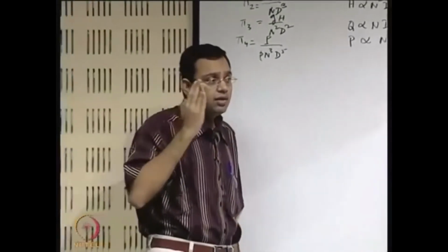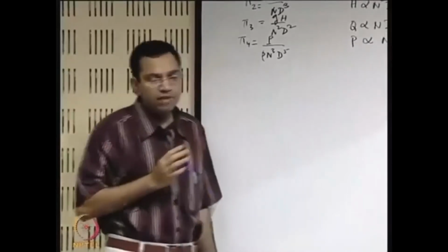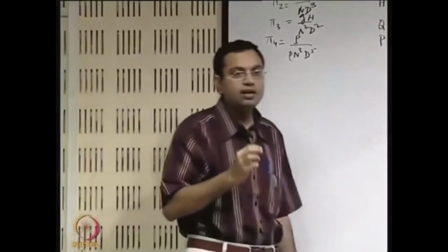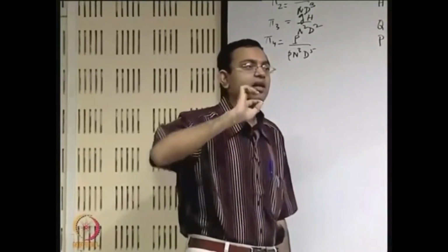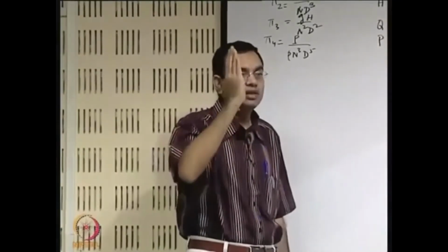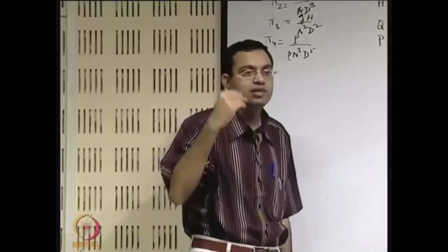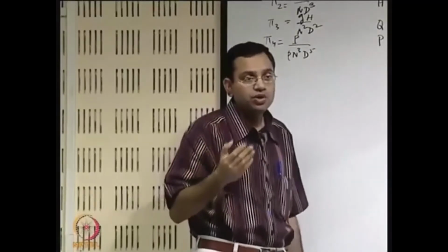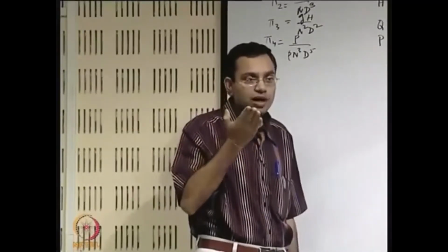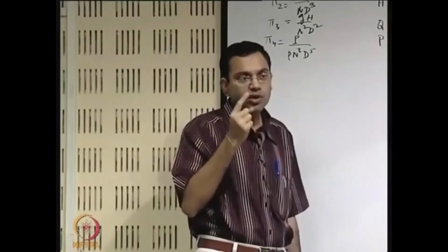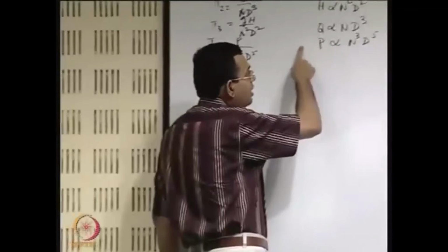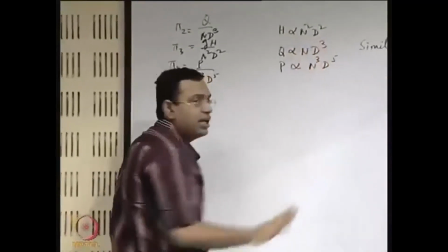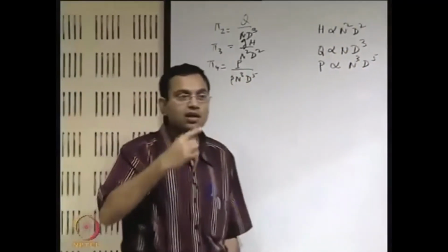And an important thing is that no matter with whatever RPM you run, the machine has a rated RPM and all its characteristics are quoted at the rated RPM. Rated means a sort of designed RPM. So, if you want to convert your experimental result at a particular RPM to the rated RPM, then you may use these relationships again with an understanding that D does not change, it is the same machine run at different RPMs.